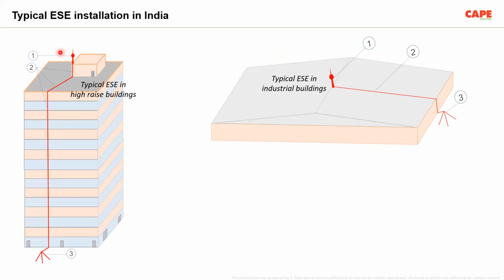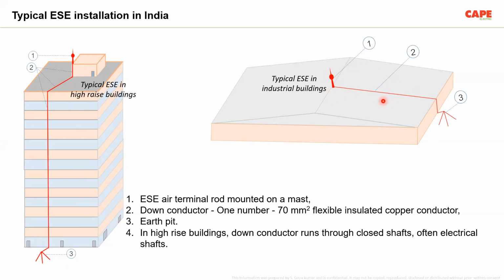Typically, this installation looks like this: imagine you have a multi-storied building. There is one rod, and a down conductor connected to the earth pit. In an industrial shed, there is one rod and a long down conductor connected to one earth pit. And always this down conductor is a 70 square millimeter flexible copper wire. And the earth pit is sometimes a pipe or a tube or a plate, or sometimes 2-3 plates and so on. So this is how lightning protection is installed in India. In high-rise buildings, this down conductor is even running through a closed shaft, and often through the electrical shaft, which is a violation.